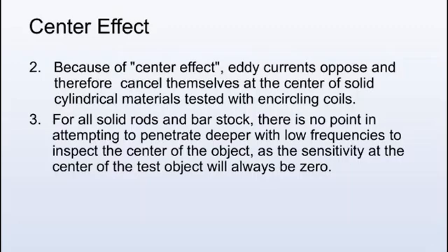For all solid rods and bar stock, there is no point in attempting to penetrate deeper with low frequencies to inspect the center of the object, as the sensitivity at the center of the test object will always be zero.